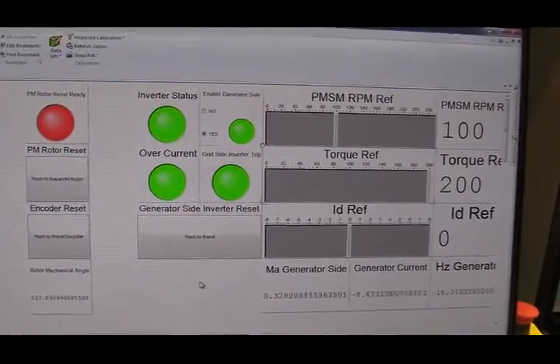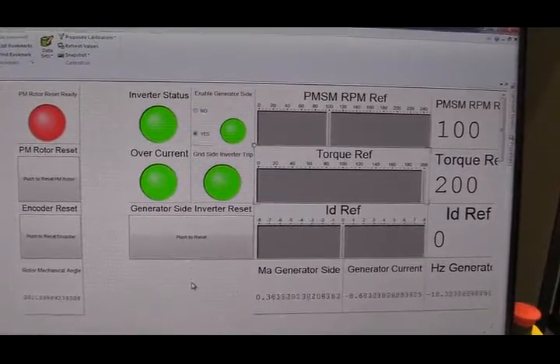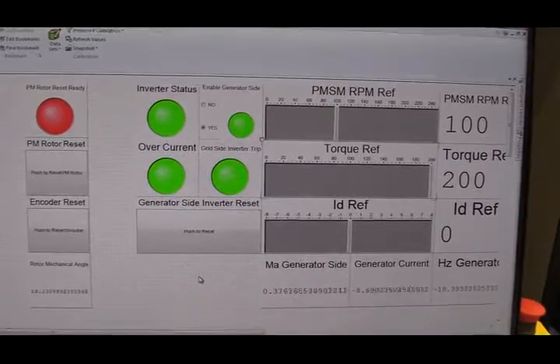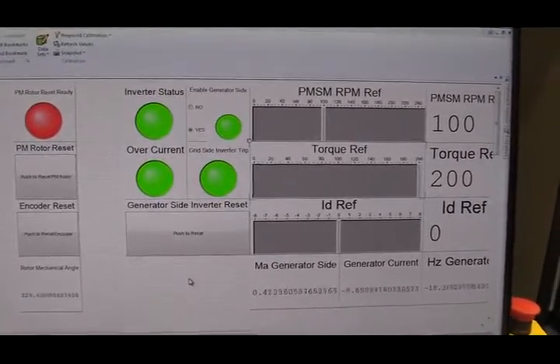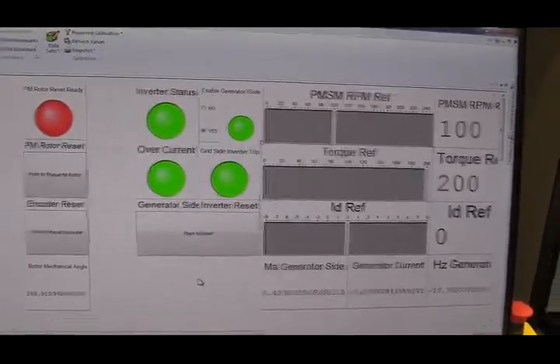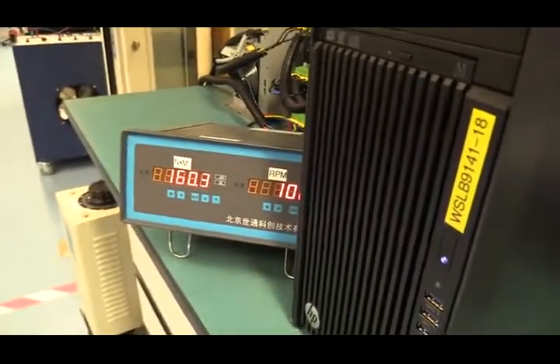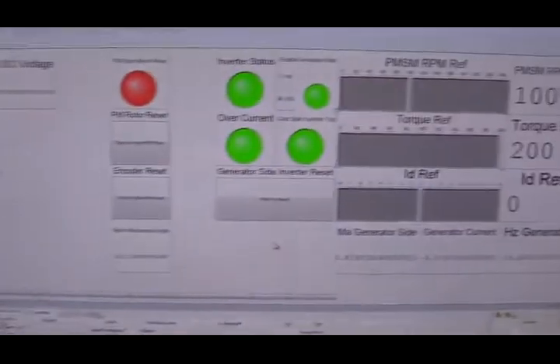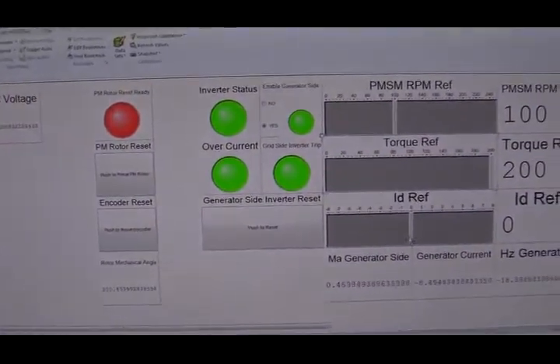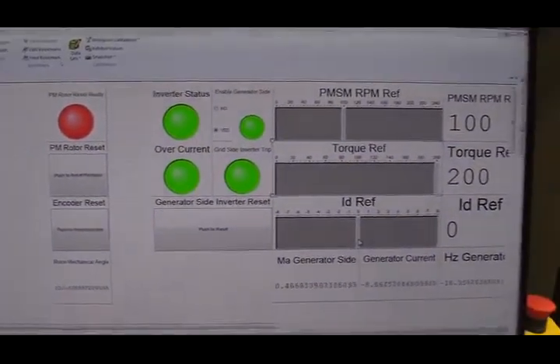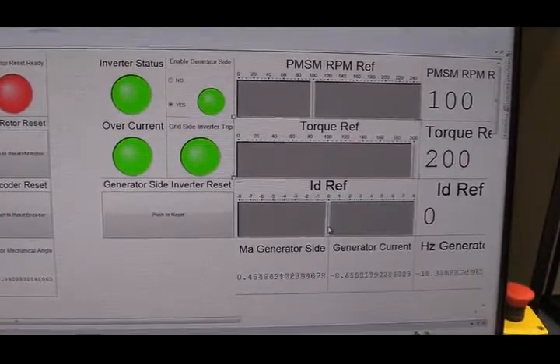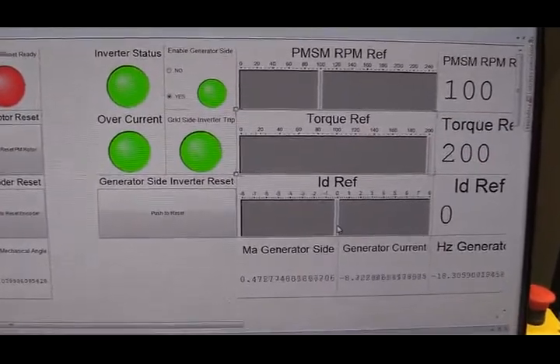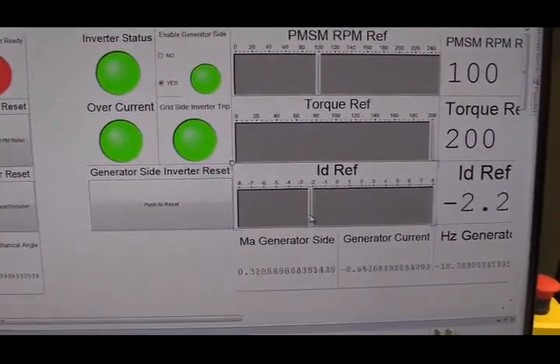So right now, the PMSG is running at 100 RPM. And my torque reference value is 200 Nm. The actual torque from PMSG is 160. If I have some minus Id current here, in theory, we should have more torque from PMSG. Let's take a look.